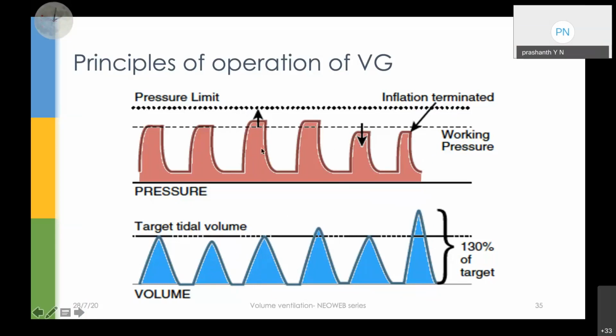You can see this here. The tidal volume, the third thing, is achieved here. Then it thinks, okay, this is the pressure it has to give, and the next breath it actually gives the same pressure, a little bit more than the working pressure, and you see the tidal volume has increased. Then it realizes, oh, this pressure is causing an increase in the tidal volume, let me decrease it, and now it decreases it again.